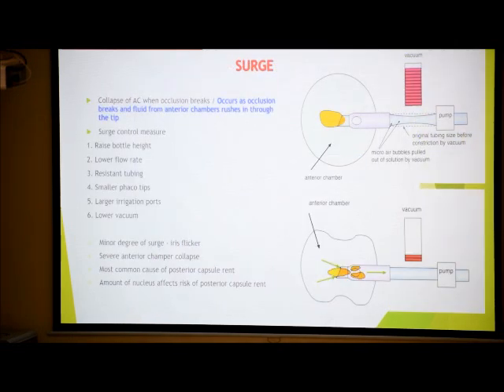Surge: the collapse of the AC when occlusion breaks and the fluid from the anterior chamber rushes into the tip. Surge is controllable, as there are factors in the machine, and also key factors where the surgeon can modulate the possibility of surge. Raising bottle height, surge will be less. Lower the flow rate, surge will be less. Resistant tubing, surge will be less. Smaller phaco tip, large irrigation port, and low vacuum: these are all factors where surge will be less.